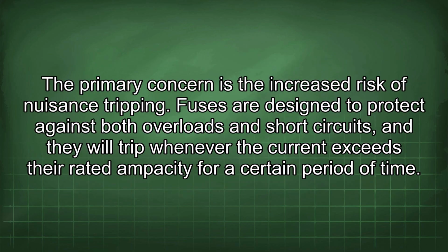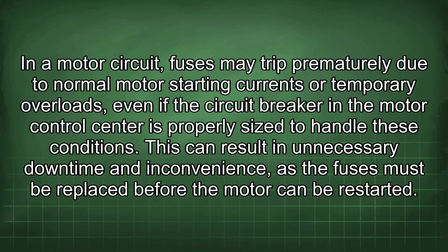The primary concern is the increased risk of nuisance tripping. Fuses are designed to protect against both overloads and short circuits, and they will trip whenever the current exceeds their rated ampacity for a certain period of time. In a motor circuit, fuses may trip prematurely due to normal motor starting currents or temporary overloads.